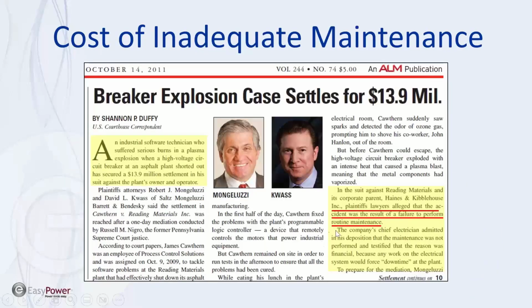So here's a case that happened in California, settled for $13.9 million. If you want some ammunition of why we need to do it, this is sometimes what it takes with upper management to understand how serious this is. So let me just read through this. An industrial software technician who suffered serious burns in a plasma explosion, so it's an arc flash, when a high voltage circuit breaker at an asphalt plant shorted out, had secured a $13.9 million settlement in his suit against the plant's owner and operator. And then down here it said the plaintiff's lawyers allege that the accident was a result of a failure to perform routine maintenance. Part of that is doing a short circuit and coordination study. That's part of 70B. That's part of the arc flash level. As far as the timing, 5 years is a guideline that's used by NFPA and the IEEE 1584 software.